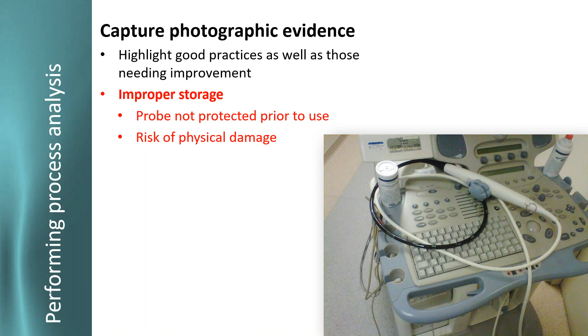So this is kind of a check sheet that Ted and I use for reporting. We basically go through this questionnaire. Are tip covers in use? Yes, no, and sometimes. Some places will use tip covers occasionally, but not all the places that they're supposed to use them. And then we go through: have we calibrated the probe before the exam? Have we done the visual inspections, the leakage testing? Are they disinfected for the minimum time recommended, and so on? How are they stored? And it's a yes or no.